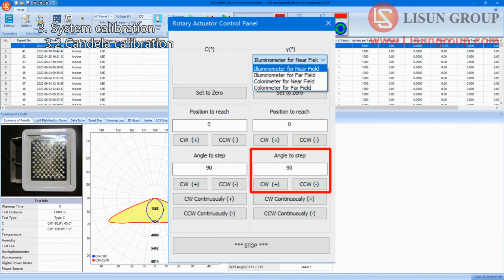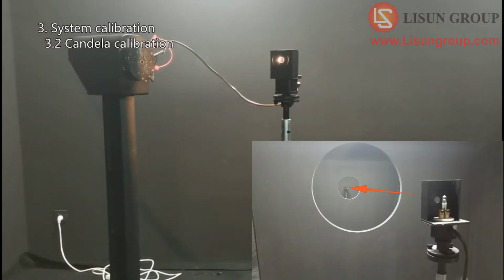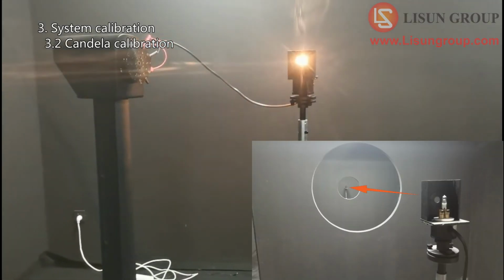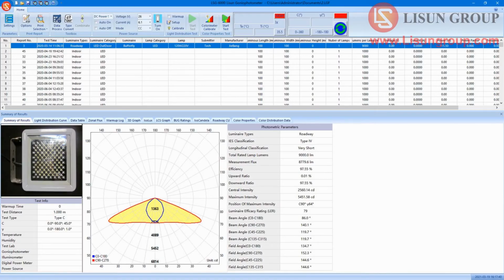Rotate the gamma angle 90 degrees clockwise or counterclockwise according to the actual situation. Make sure that the hole of the standard lamp holder faces the far detector. Turn off the other lighting inside of the darkroom. Close the door of the darkroom. The standard lamp will be stable after about 15 minutes.